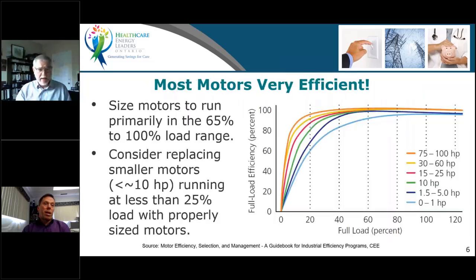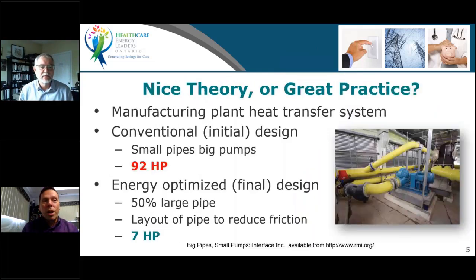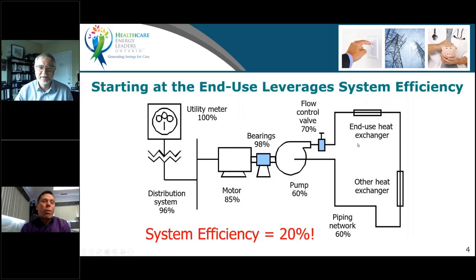Now, let's say they would not have changed it. It would have stayed at 92. 92 is calculated by the engineer. Once they go on site, I can bet you the engineer covered himself. He actually overestimated the pressure drop. So they're not going to change the pump. They're just going to add artificial pressure drop to basically match the engineering calculation. They'll throttle that valve that you were showing. They will throttle the valve. So this actually is very critical, because they will actually size the pump, size the motor, for a calculated value. And I can bet you all your pumps in all your buildings are oversized because of that.